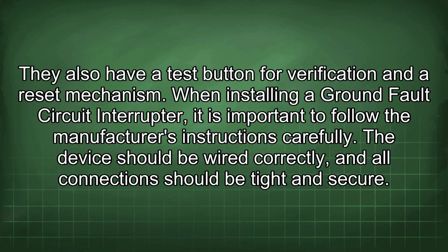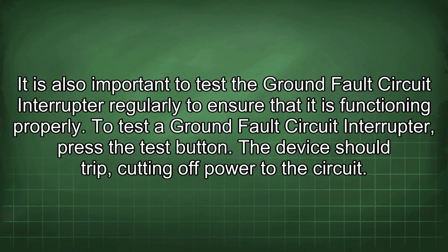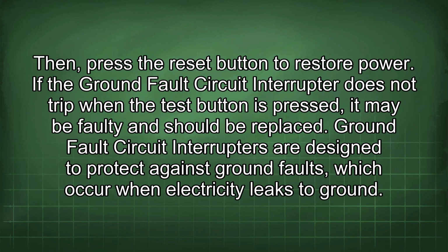When installing a ground fault circuit interrupter, it is important to follow the manufacturer's instructions carefully. The device should be wired correctly and all connections should be tight and secure. It is also important to test the ground fault circuit interrupter regularly to ensure that it is functioning properly. To test a ground fault circuit interrupter, press the test button. The device should trip, cutting off power to the circuit. Then press the reset button to restore power. If the ground fault circuit interrupter does not trip when the test button is pressed, it may be faulty and should be replaced.